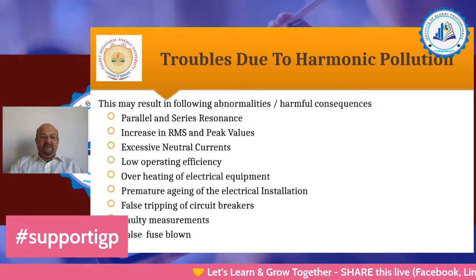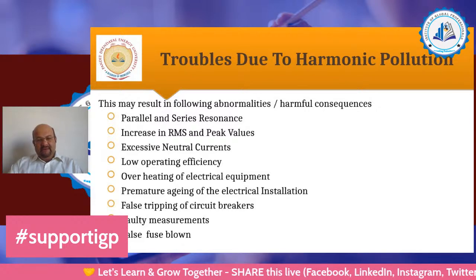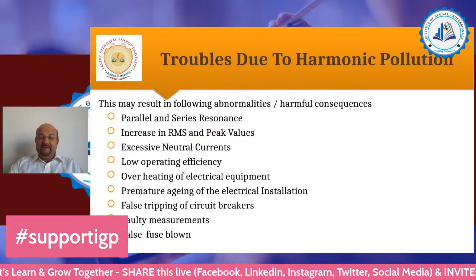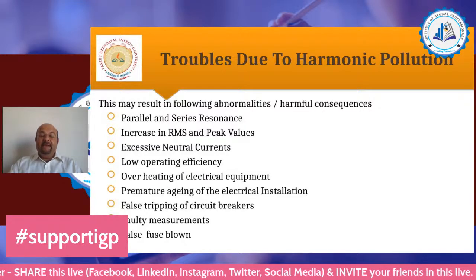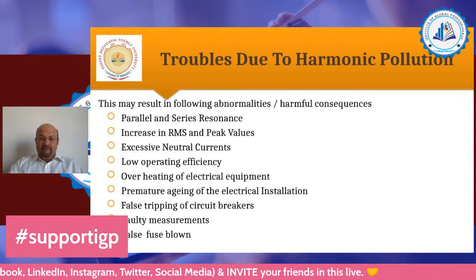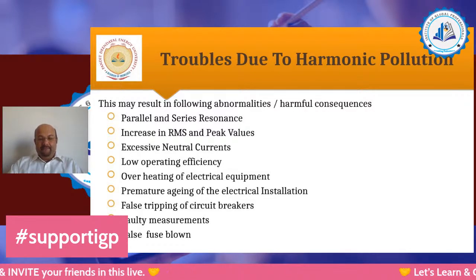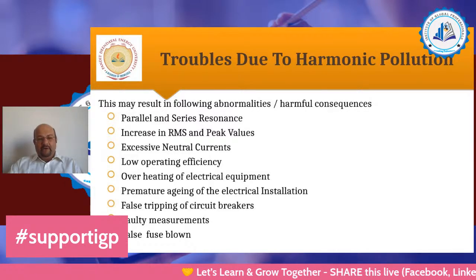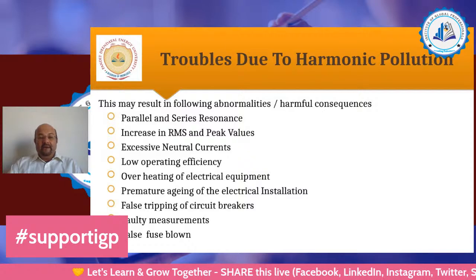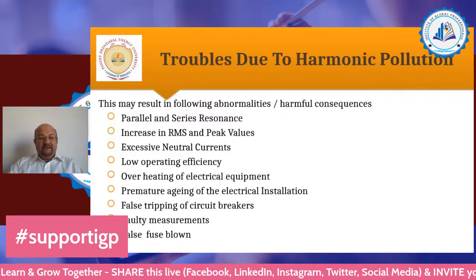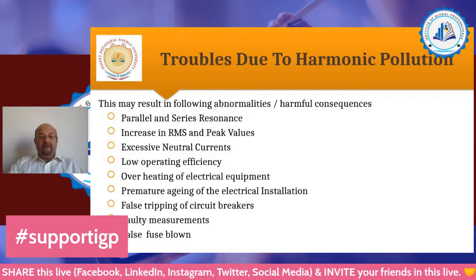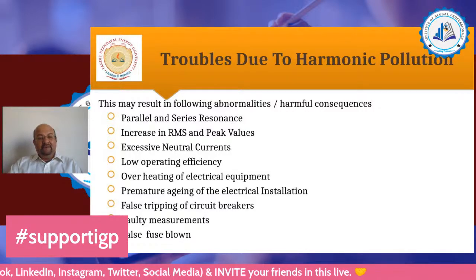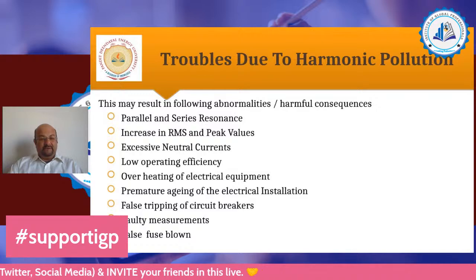Now, how does premature aging happen? The life expectancy of any electrical equipment can be considered as the life expectancy of the insulation provided in that equipment. And insulation materials are very sensitive towards heat. As I already mentioned previously, due to iron losses and harmonics, there is continuous overheating of the equipment, and due to that, the life expectancy of insulating material reduces drastically, which will result in a premature failure of the installation. False tripping of circuit breakers.